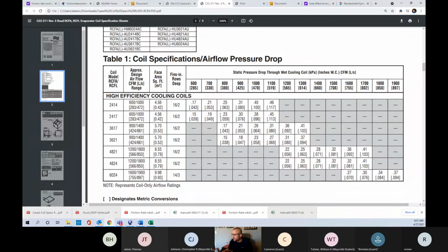Really. So if you're at 800, if we were going back to the whole 400 CFM per ton, you're at 0.23. So trying to push 1,100 CFM through that coil may end up being a problem, and that's what this is going to tell us. So that's your 0.45. All right, so let's just use that as your coil pressure loss. So you would write in 0.45.